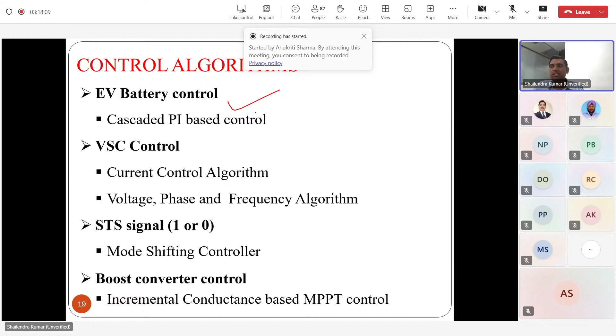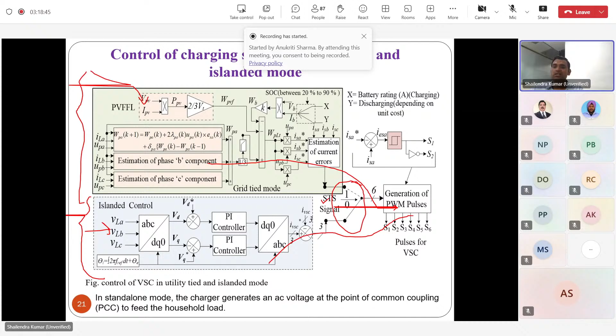As I told you, it is operating in grid-tied mode as well as in standalone mode. So we have separate control for current control and separate control for voltage control. This decision will be taken by the static transfer switches, which we have connected in the first topology. So the static transfer switches will define whether the converter is going to be controlled in current control mode or in voltage control mode.